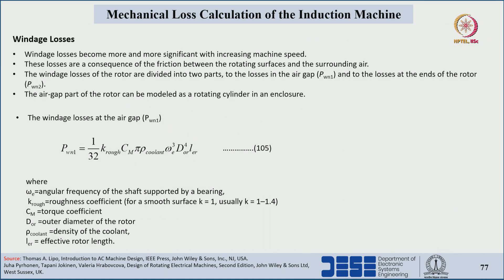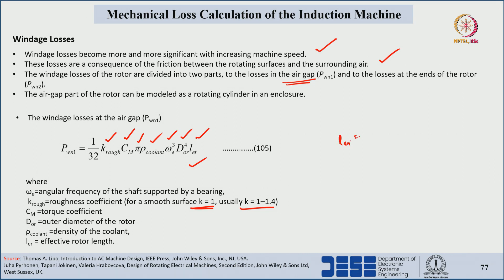The next component is windage losses. Windage losses are more significant at higher speeds — more speed means more friction with respect to the air present inside the machine. These losses are the friction between the rotating surfaces and air. The windage losses with respect to the air gap are given by: (1/32) times the roughness factor — which is 1 for smooth surfaces and 1 to 1.4 for others — times torque coefficient Cm, times pi, times coolant density, times angular frequency of the shaft, times rotor outer diameter to the power 4, times rotor length L_er (considered as L_e when stator and rotor lengths are the same).